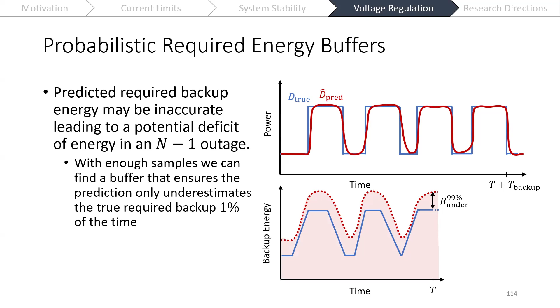Sometimes in our backup energy requirement, our predicted model is saying that we need less energy than we'd actually need. If we look over many different traces, testing over lots of potential loads that our data center could have, what we can do is find this 99% barrier around what the actual required backup energy would be. And we can say that 99% of the time, our predicted backup energy requirement will stay within that buffer. If we add that buffer to what our predicted lower limit requirement would be, we can find a limit that at least 99% of the time, our required backup energy will fall below.